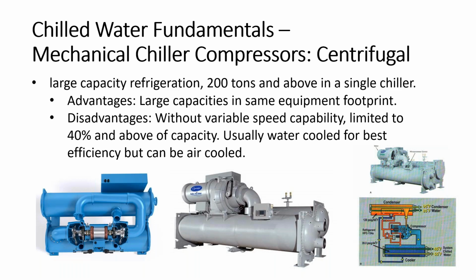The diagram here at the bottom right gives you an idea of what it does and the temperatures we look at. The temperature is 10 degrees on the evaporator, the cooler side, and then it compresses up to 95, 85 degrees on the condenser water side. So these are typical of the range of operation for these chillers. And this is always the case where you rate the chillers and the cooling towers based on the condenser and how you size them. But they are designed to move massive amounts of refrigerant. I've seen 8,000 tons in one machine. So they can do a lot of work. One of the drawbacks though, for the early ones, was that you could not go to a low capacity.